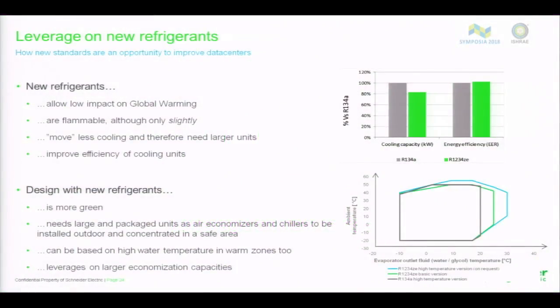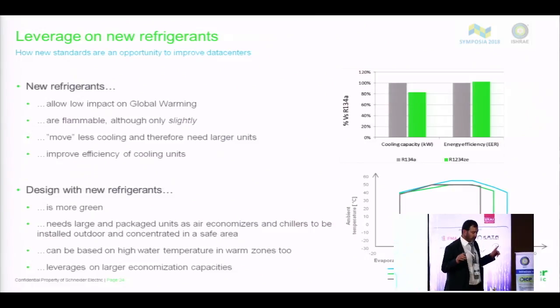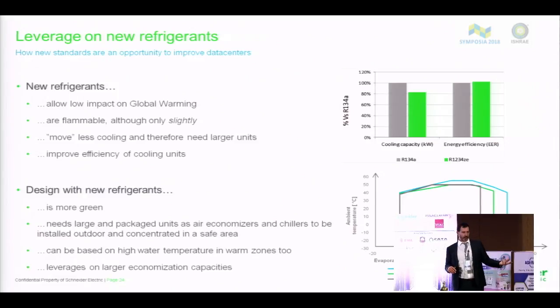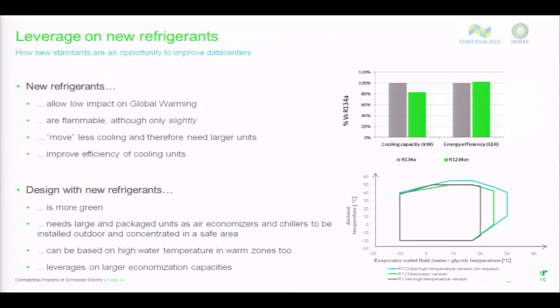Last point, refrigerant. On the refrigerant, probably we may have a session dedicated only to that. There are thousands of white papers that have been shared and distributed in the last few years. There is a lot of discussion about what the new refrigerant scenarios and the new choices will be. What is true is that at this moment, the availability of traditional refrigerant is going down. The new refrigerant is rising, especially on large installations. So today, there are 2 traditional, not very old refrigerants, that are the R410A and the 134A. The R22 is out of the equation because it will be banned. It is banned.